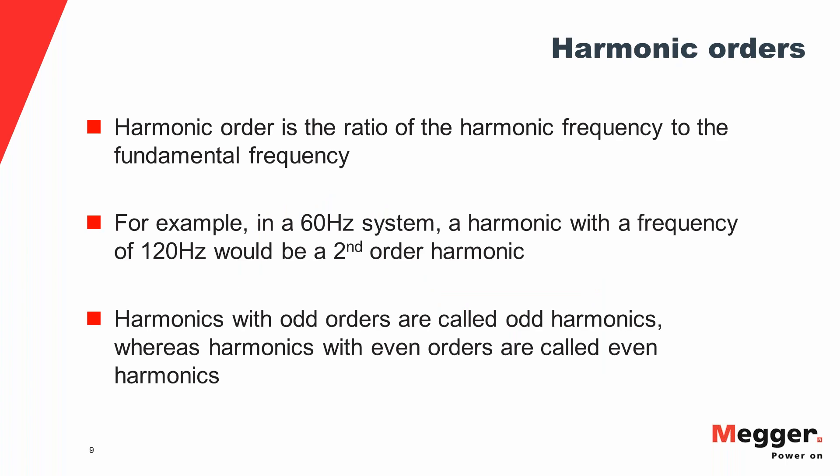On the previous slide it said 20% third harmonic and 20% fifth harmonic. Third and fifth are called harmonic orders. Harmonic order is the ratio of the frequency of the harmonic to the fundamental frequency. A third harmonic means the frequency is three times the fundamental — 180 Hz for a 60 Hz system. Fifth harmonic is five times 60, which is 300 Hz. Frequencies with odd orders are called odd harmonics — third, fifth, seventh, ninth, eleventh — and harmonics with even orders — second, fourth, sixth, eighth, tenth — are called even harmonics.